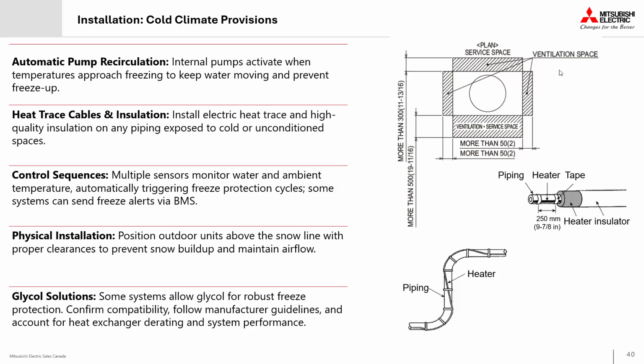We're almost always seeing insulated pipes on our external, but sometimes heat trace as well. A lot of the modern systems today will use automatic pump recirculation, which helps keep water moving throughout our heat exchanger and lowers the risk of ice formation in our heat exchanger when those outdoor temperatures drop. It's also mandatory for most manufacturers to install the outdoor units above local snow grade, making sure there's plenty of room for airflow, drainage, and service access, because these are systems that will basically always be running in heat pump mode.